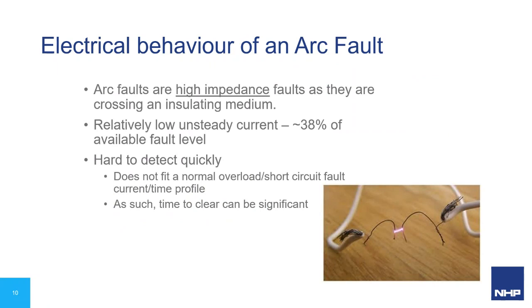So now to have a bit of a look at the electrical behavior of an arc fault. What a difference between this and some of the other things that we see in overload and short circuit is that these arc faults are high impedance faults. So air is a very bad conductor, so it actually is far lower than a short circuit current. About 38% seems to be the rule of thumb, but generally the numbers quoted are usually between 30 and 40% of the available fault level. So what that means is it's very hard to detect.